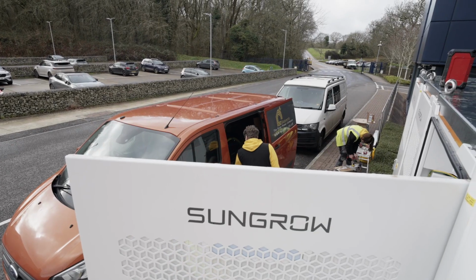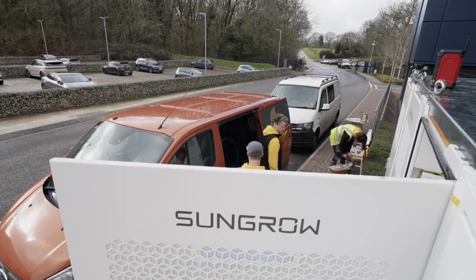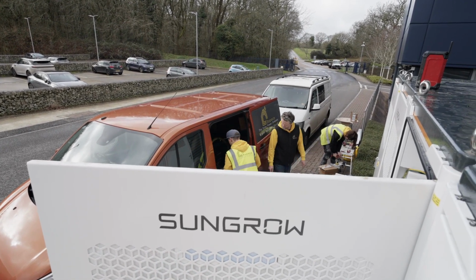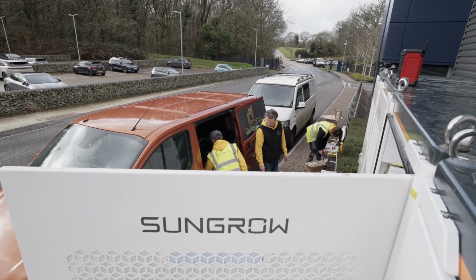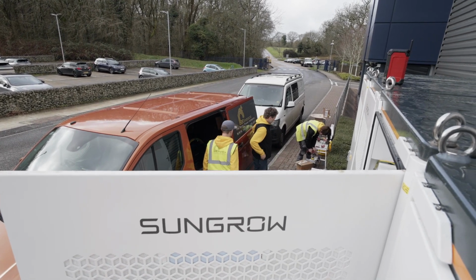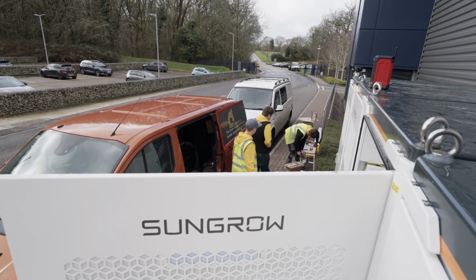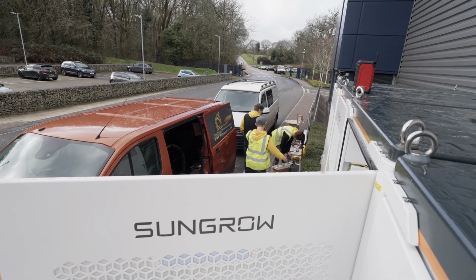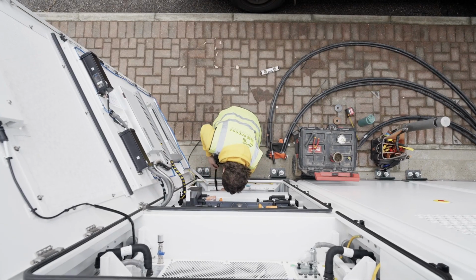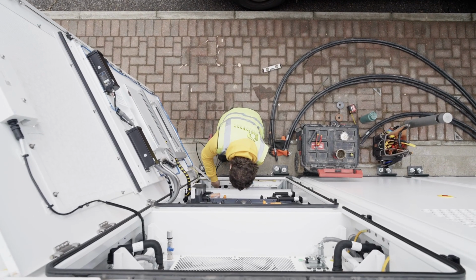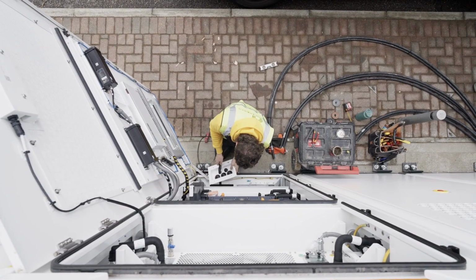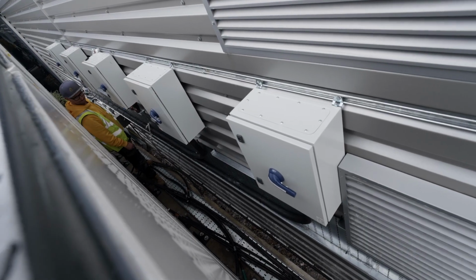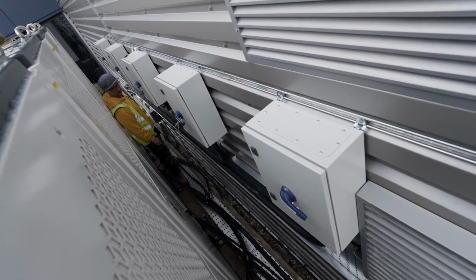Some of the main features of the power stack are cell-level safety and electrical safety, with an additional three levels of safety including multi-layer overcurrent protection, anti-arc protection, and a fast-breaking DC protection circuit. The fire safety system has a built-in smoke sensor which can automatically detect smoke, detect fire, and shut down the system remotely before it causes damage.